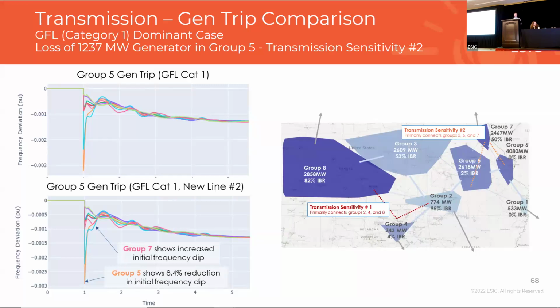When we compare these charts and look specifically at some of the groups most affected, we see group 7 shows an increased initial dip in frequency that was not as present without the transmission. We also see group 5 shows a reduction in the initial frequency dip, whereas here it was clearly going below 0.003 per unit frequency, and now it's staying above 0.003 per unit frequency.